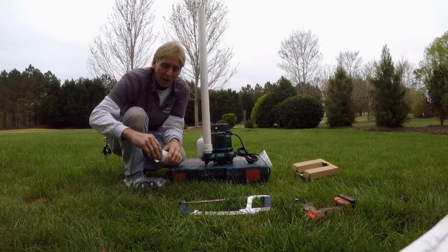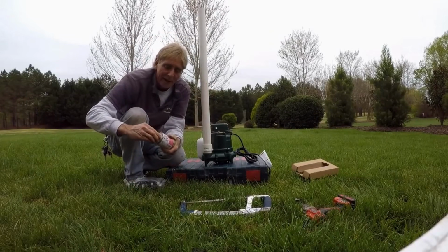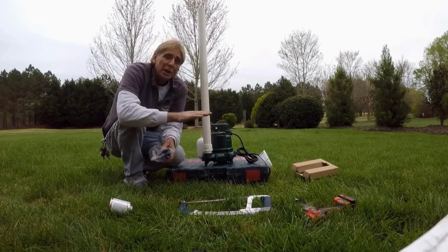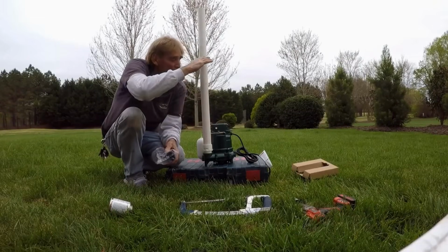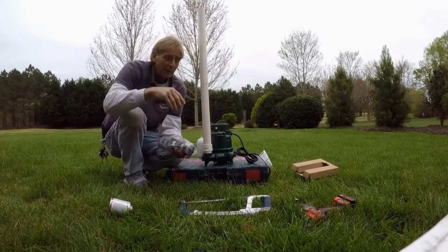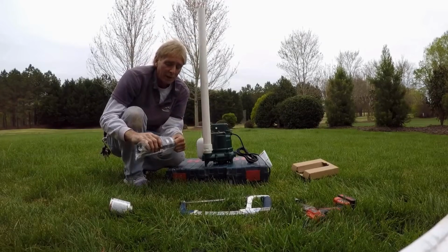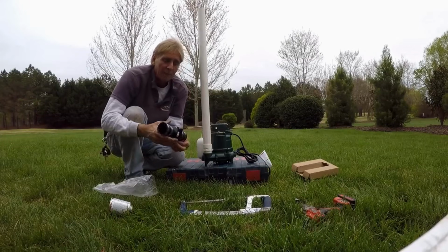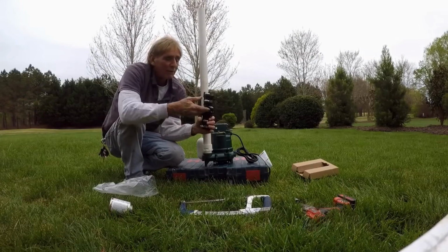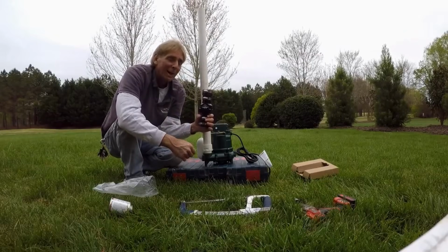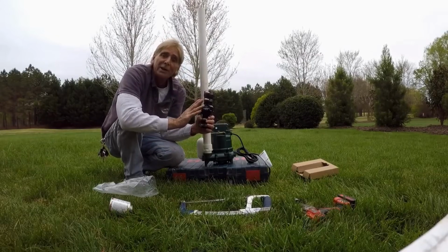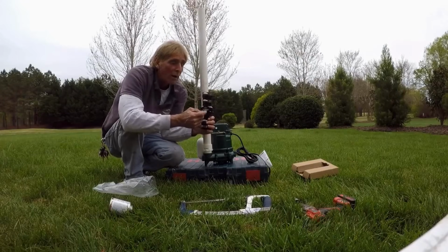We're ready to actually go ahead and install this in the sump basin down below. We'll put this all in, put the lid on top. Remember, I drilled the hole. That'll come and cover it up to wherever. And then we'll put this check valve on there, because we don't want the water that we're lifting up to come back down into the pit. So always, whatever check valve you use, you're going to see some type of an arrow, or it may say flow. Make sure you're going the right direction when you put it on.